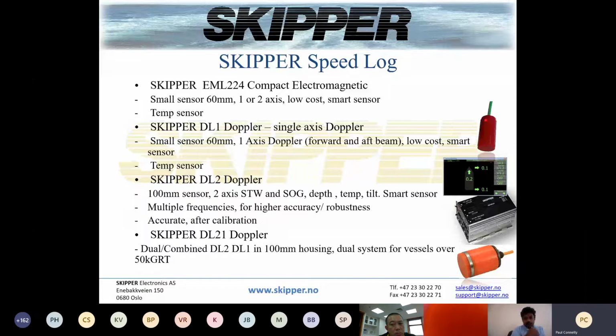If you combine the DL2 and the DL1, you get what we call the DL21. This is actually two independent systems, two electrically isolated systems, but they're both put in the same set of housings. The sensor is still a 100 millimeter sensor, but inside you have the DL2 going at 270 and 900 kilohertz, and the DL1 going at 700 kilohertz. These run simultaneously and independently of each other.